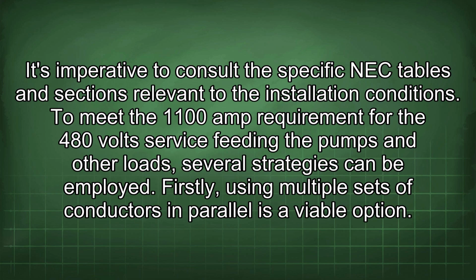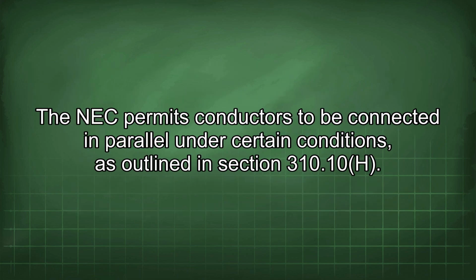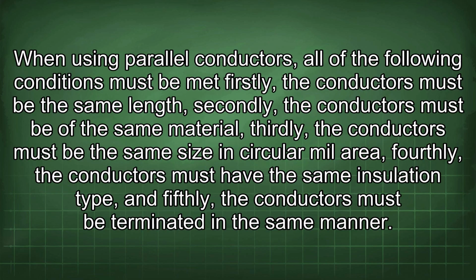To meet the 1100 amp requirement for the 480 volt service feeding the pumps and other loads, several strategies can be employed. Firstly, using multiple sets of conductors in parallel is a viable option. The NEC permits conductors to be connected in parallel under certain conditions, as outlined in Section 310.10(H). When using parallel conductors, all of the following conditions must be met. Firstly, the conductors must be the same length. Secondly, the conductors must be of the same material.